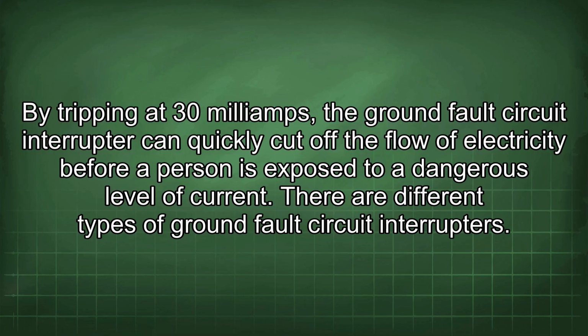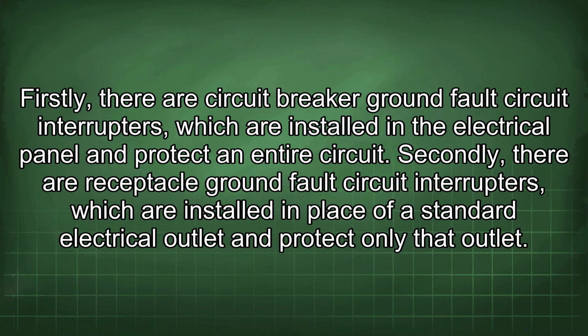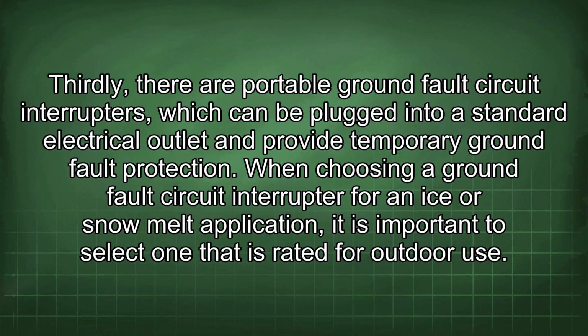There are different types of ground fault circuit interrupters. Firstly, there are circuit breaker ground fault circuit interrupters, which are installed in the electrical panel and protect an entire circuit. Secondly, there are receptacle ground fault circuit interrupters, which are installed in place of a standard electrical outlet and protect only that outlet. Thirdly, there are portable ground fault circuit interrupters, which can be plugged into a standard electrical outlet and provide temporary ground fault protection.